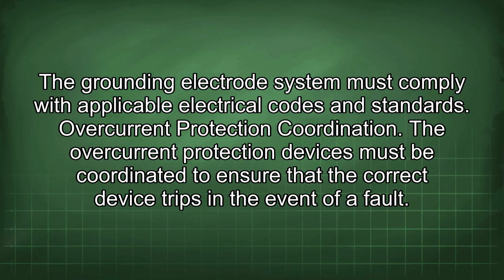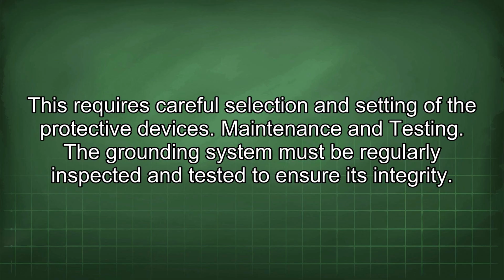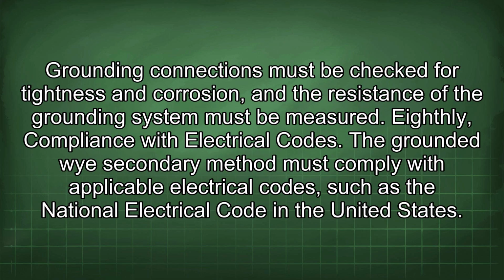Overcurrent protection coordination. The overcurrent protection devices must be coordinated to ensure that the correct device trips in the event of a fault. This requires careful selection and setting of the protective devices. Maintenance and testing. The grounding system must be regularly inspected and tested to ensure its integrity. Grounding connections must be checked for tightness and corrosion, and the resistance of the grounding system must be measured.